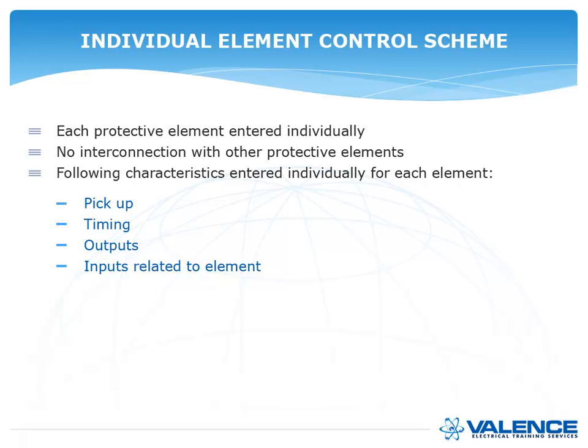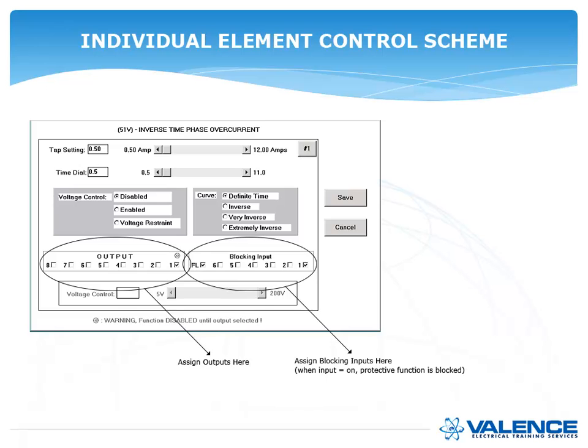And here is from a Beckwith relay. This is an individual element control scheme. You can see on the top, you type in the tap setting, you type in a time dial. You select what kind of voltage control you're going to use. You choose your curve, and then you put a checkbox in every output that will turn on when this element turns on. And then if you want to block it with anything, then you just look at the blocking input. So in this case, if input 1 operates, this element will be blocked, or if the fuse loss, which is what that FL stands for, then this element will be blocked.